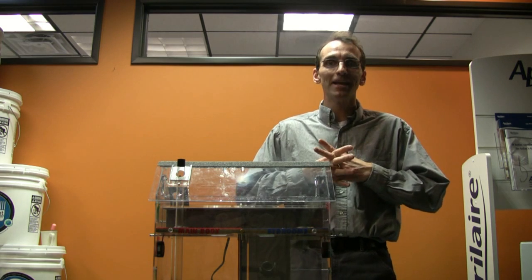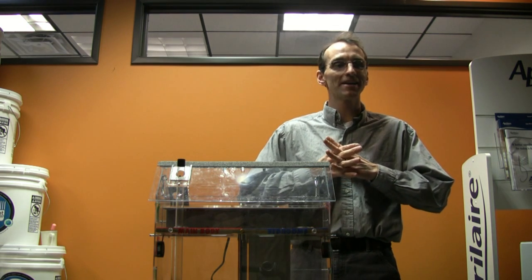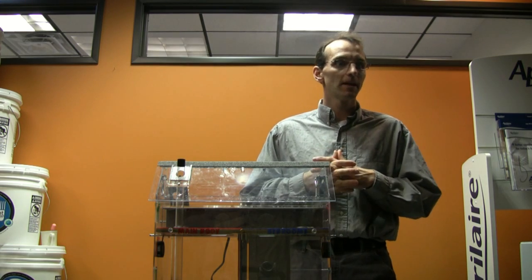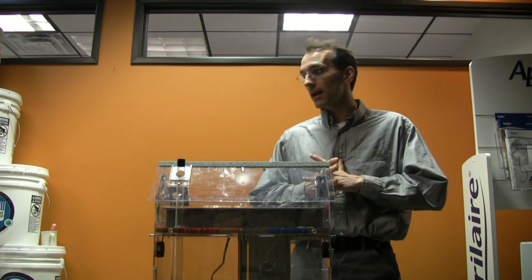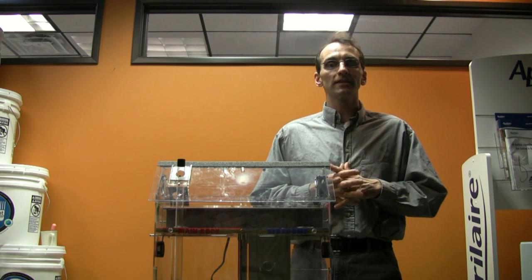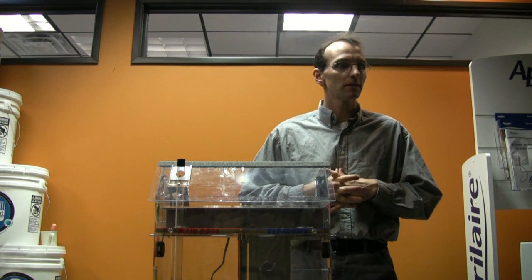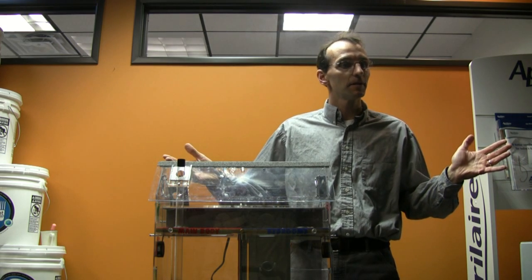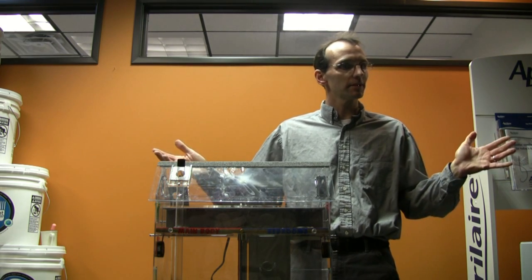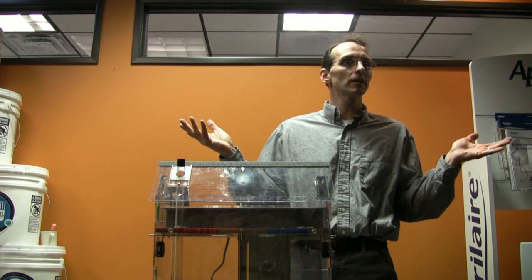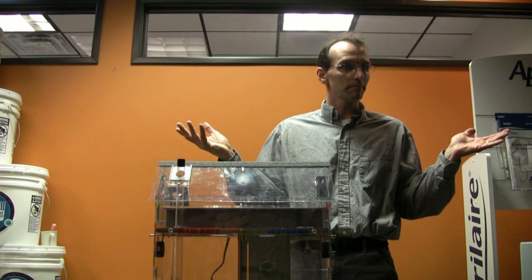Here's a carbon monoxide alarm, right? It's going to annoy you. If you have a carbon monoxide alarm in the house, sure. I've actually been in houses that have carbon monoxide detectors where I've hit the button to see what the memory says. It says that it's been to 29 parts per million, which if it's 30, you have to evacuate the building. But the homeowners had never even heard the thing go off, ever.